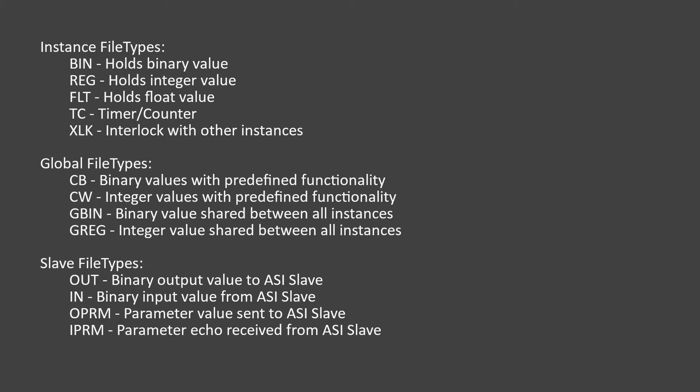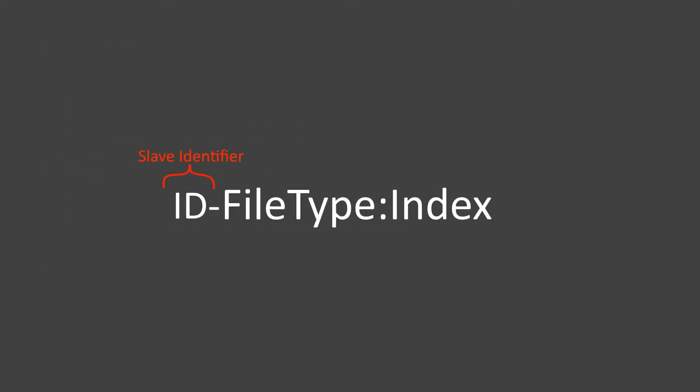Instance addresses are local to that conveyor section only. The register 0 of one conveyor section is different from the register 0 of another. Worth noting is that each conveyor section is given a certain amount of memory for instance addresses and that this limit cannot be exceeded. Global addresses are common between all conveyor sections. The global register 0 address is the same between all conveyor sections, for example. Slave addresses store values that are read from and written to by slaves. These have an extra specifier at the start that determines which slave the address is referring to. Note that this specifier is just a placeholder ID within the Ladder and it will later on be mapped to a real slave address.